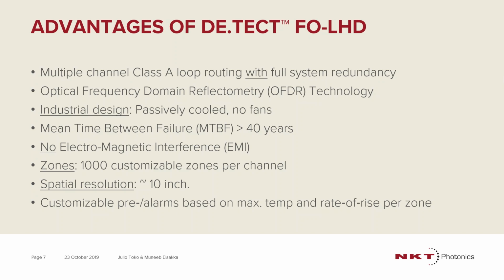One advantage as well to fiber optic linear heat detection is there is no electromagnetic interference, since you do not have metal in the cable with the more traditional LHD systems. Of course, having the ability as well to program 1,000 customizable zones per channel with a spatial resolution of about 10 inches. So essentially, you can set up a zone or a hazard every 10 inches along the full length of your cable. You can also customize pre-alarms based on maximum temperature, as discussed, or rate of rise per zone, which gives you a lot of flexibility over the more conventional LHD systems.